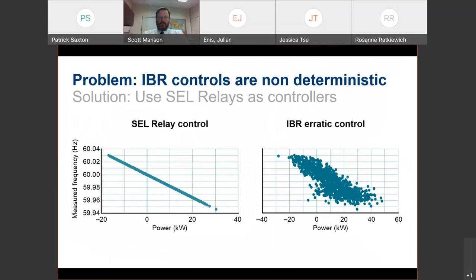So the inherent behavior of inverters is non-deterministic many times because their controls are relegated to errors that humans make with firmware, with settings changes. Ask yourself a question. How many times has the inverter manufacturer had to update their firmware on the inverters that you purchased? Every time they change that firmware, there's a possibility of it not working like you originally commissioned, tested, and proved out. There's a very good chance that you've just made obsolete all of the work in the surrounding 10-county area in a protection system and a control system because that inverter might behave differently than originally tested. That's a huge problem, and it's happening today because they're non-deterministic, because they're not mature, and they're becoming too complex.